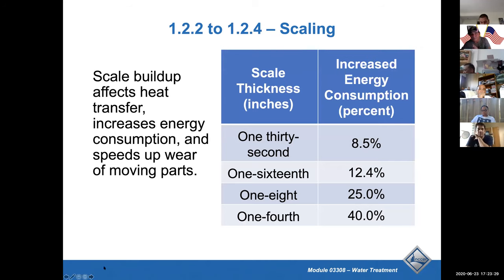So that's one thing you gotta watch is insulation. Make sure insulation's not wet on your air conditioning plant. Okay. And look at these different percentage of scale buildup on piping. If it's any of these from 1/32 to 1/4, look at the big difference in percentage of energy consumption you're using. So that's not good.